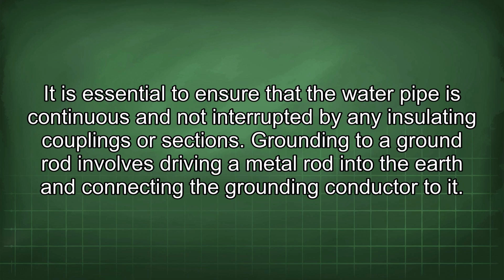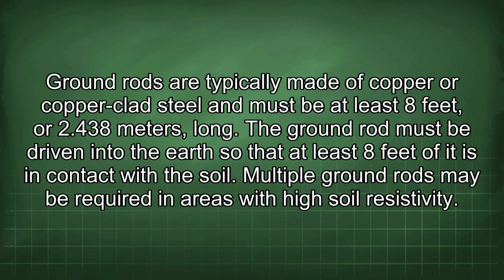Grounding to a ground rod involves driving a metal rod into the earth and connecting the grounding conductor to it. Ground rods are typically made of copper or copper-clad steel and must be at least 8 feet, or 2.438 meters, long. The ground rod must be driven into the earth so that at least 8 feet of it is in contact with the soil. Multiple ground rods may be required in areas with high soil resistivity.